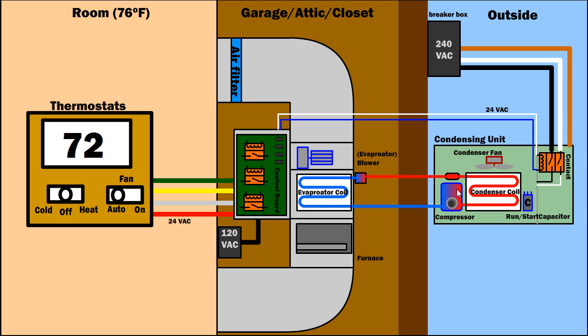For the heater on the furnace side, well, let's first of all set it to heat. Set the thermostat to 80 degrees. It's hotter than, it's set to a higher temperature than the room temperature. Once again, 24 volts AC goes through here and then it sends back the signal to the controller board. And then the controller board turns on the blower and then it closes another contact, another relay. And that turns on the furnace.